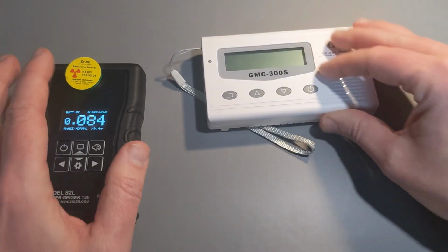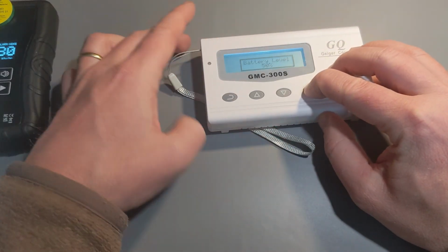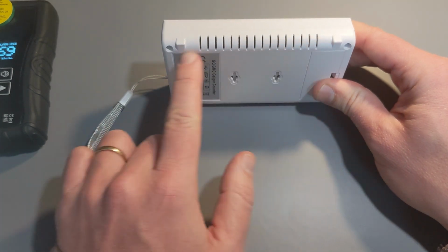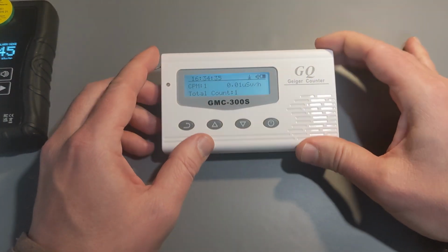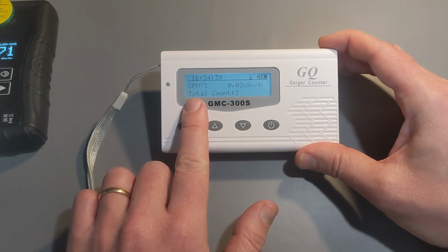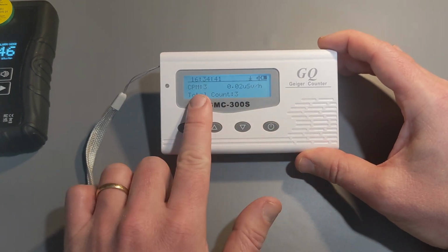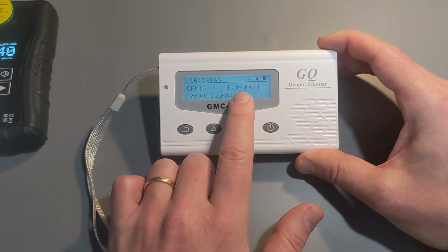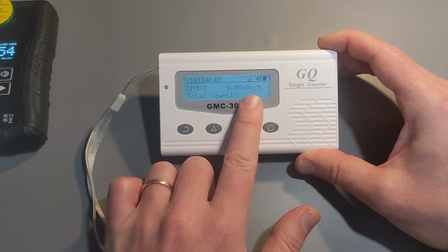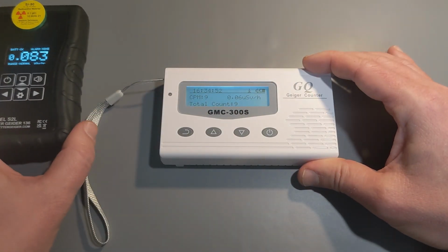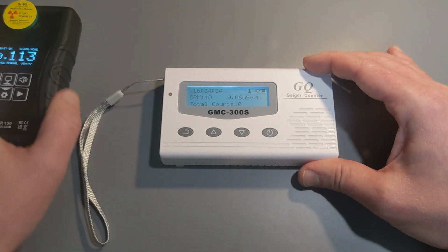And to take the other example here, this has a Geiger tube inside, and it's quite sensitive to beta. And we'll get into the energy question as well, but for now we can see, you hear, I don't know if it goes through the audio, but you hear a count here and there, and there's a dose rate here of 0.04, or it hasn't quite settled, but 0.0 something microsieverts per hour. So not super far off from here.